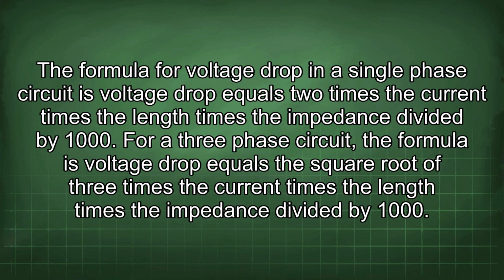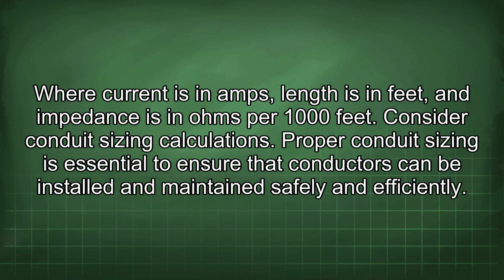The formula for voltage drop in a single-phase circuit is voltage drop equals 2 times the current times the length times the impedance divided by 1000. For a 3-phase circuit, the formula is voltage drop equals the square root of 3 times the current times the length times the impedance divided by 1000. Where current is in amps, length is in feet, and impedance is in ohms per 1000 feet.